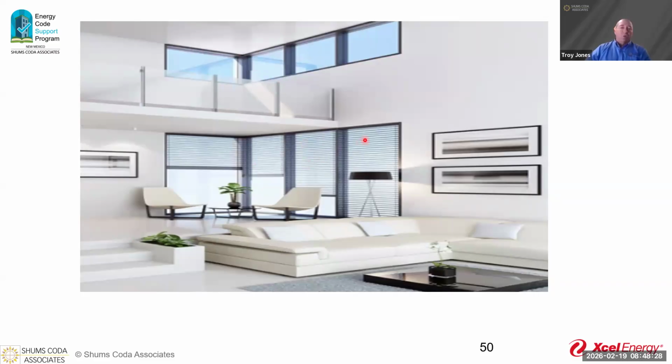Another tricky one, and this is one that on plans, I can say I made this mistake. I required only one daylight zone, and my supervisor came back to me after the inspector caught it out in the field and asked me what I was thinking. I had totally missed the ceiling right here, and I was basing everything off of the monitor zones up here. So just trying to keep folks from doing some of the mistakes I've done.